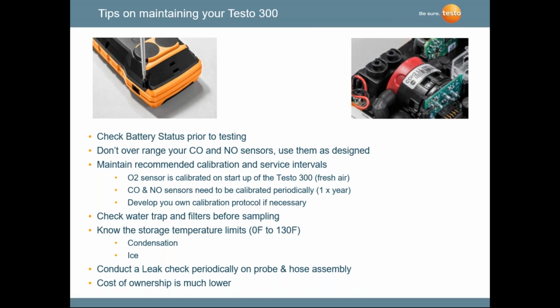Maintain recommended calibration intervals and just remember that every time you turn on an instrument, a Testo 300, you're calibrating the oxygen sensor to the ambient fresh air in the room. So every time you turn the instrument on, you're actually calibrating the oxygen sensor for ambient air, which is 21% oxygen. Don't put the probe in the stack when you turn the instrument on, unless you're using that high-end 300 that I talked about that goes up to 30,000 ppm, because that has an extra pump in it, which actually brings the sample air from the side of the instrument.